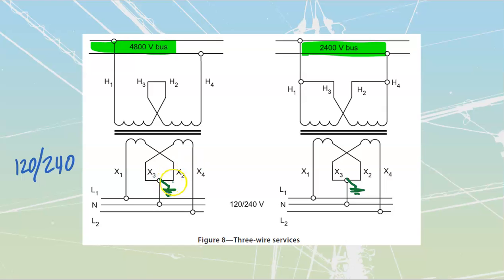But really what we're going to find out is that the reason we ground the neutral over here is to stabilize system voltages, but more importantly because all of my bond system is also going to be tied back to that ground, and then I'm going to be able to deliver all of my current through my ground system.